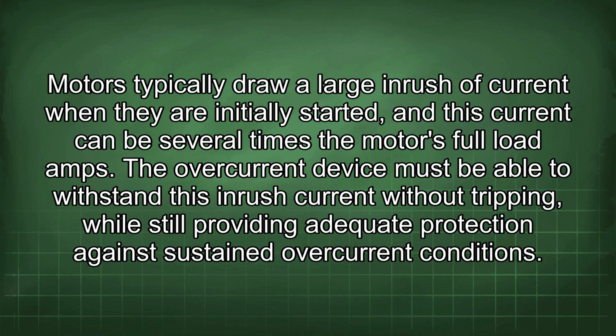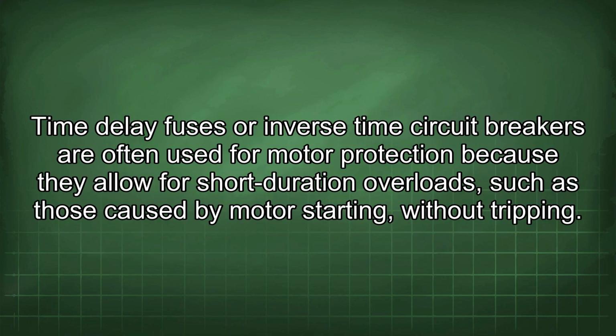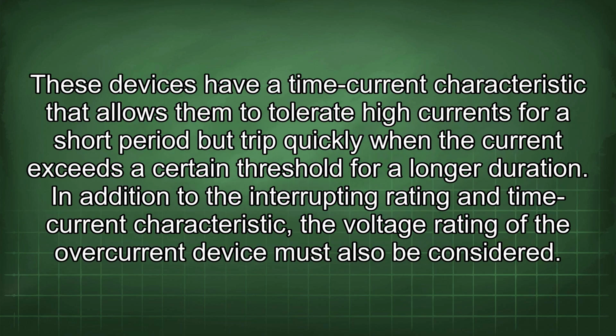Time delay fuses or inverse time circuit breakers are often used for motor protection because they allow for short duration overloads, such as those caused by motor starting, without tripping. These devices have a time current characteristic that allows them to tolerate high currents for a short period, but trip quickly when the current exceeds a certain threshold for a longer duration.